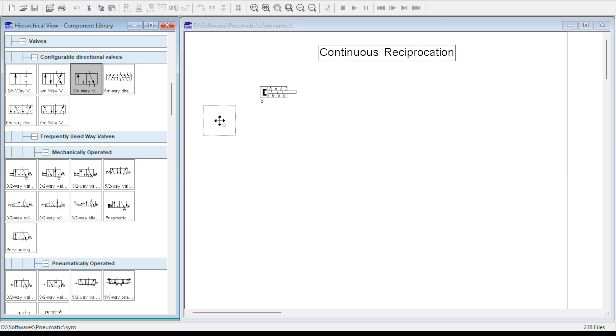The 3x2 DCV can be configured by double clicking on it, and you can find out the kind of actuation that you can give to the left hand side and the right hand side. So the two positions of this DCV are mentioned here, where the normally open position will be to the left actuation and the normally closed position will be to the right actuation, and by default we want the DCV to be a normally closed DCV. The method of actuation for both the sides of the DCV is set to pneumatic, which makes this DCV a double pilot actuated 3x2 DCV.